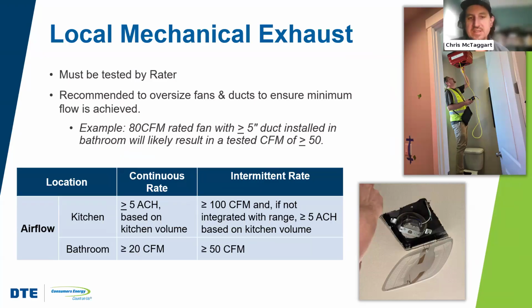Bathrooms need to move at least 50 CFM if intermittent, so basically switch operated, or 20 CFM if continuous. Kitchens need to have 100 CFM intermittent, so again switch operated. But then if it's continuous, or if you're using a remote mounted fan, that rate could be potentially higher, and it's based off the volume of the kitchen. So a little bit more complex and specific, but regardless, it has to be tested.